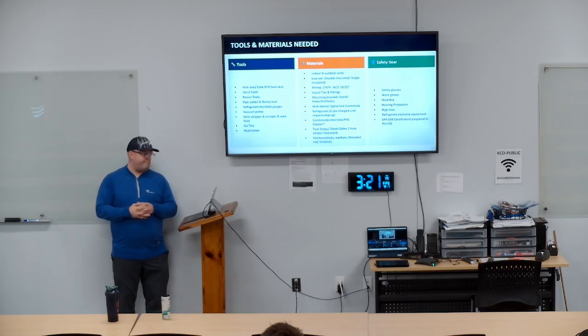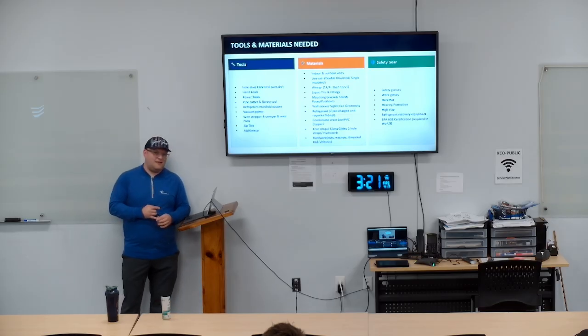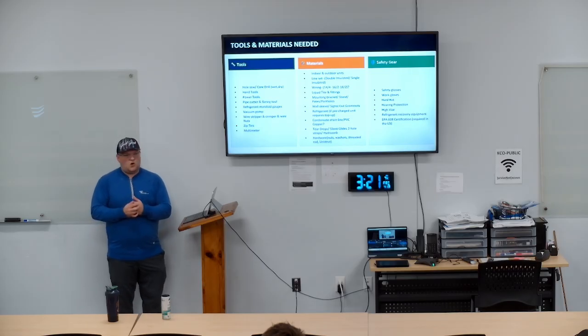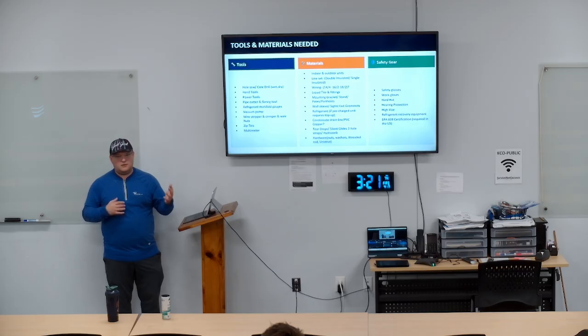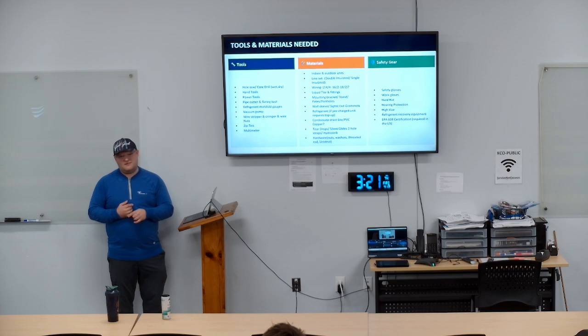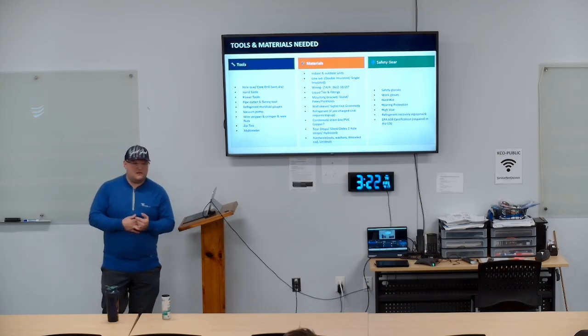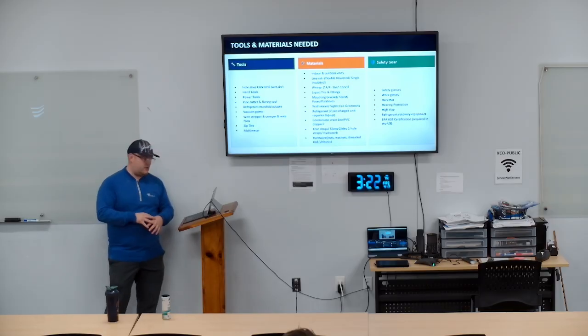Well, as far as condensate drains, when you guys go to site, always find where our condensate drops are. The designers have been getting better about it, but they don't always show us where we're running our condensate. They're like, oh yeah, just run the condensate. Always ask the question. If you see condensate going out a wall, or someone says, hey, we're taking it out, just ask me, hey, can we do that? Some splits you can't do that with. If it's a designated IT room and it's going to run cooling year round, we probably shouldn't take it outside. Now, could we? Yeah, because normally in the winter, the reason it's creating moisture, condensation, is humidity, but it's dry in the winter, so you don't have to worry about it. That's a little deeper. We can have that discussion another day if you don't quite understand it, because that's a process.